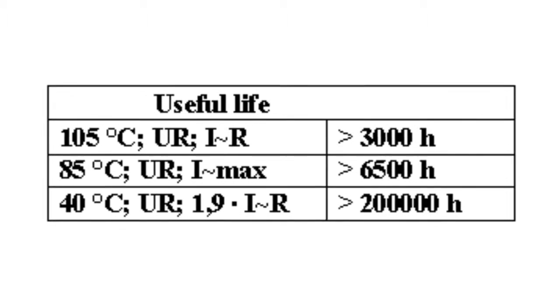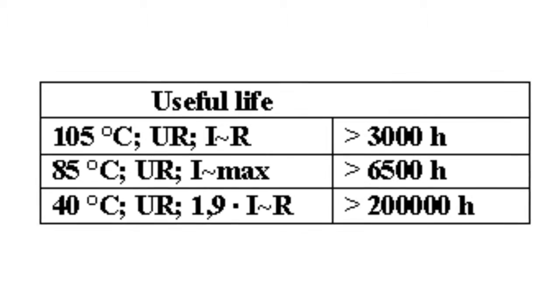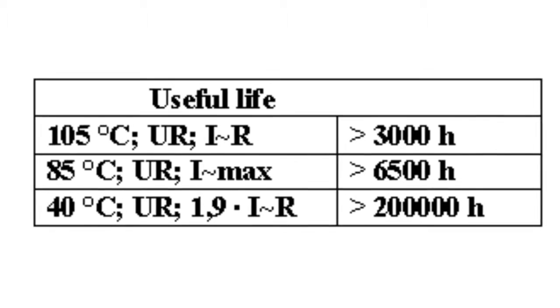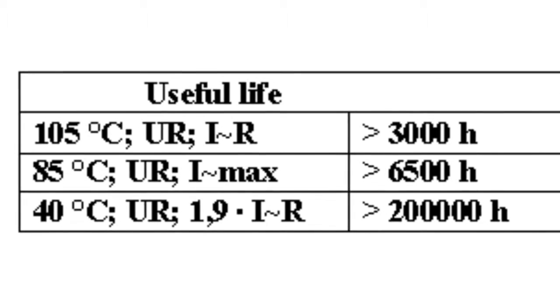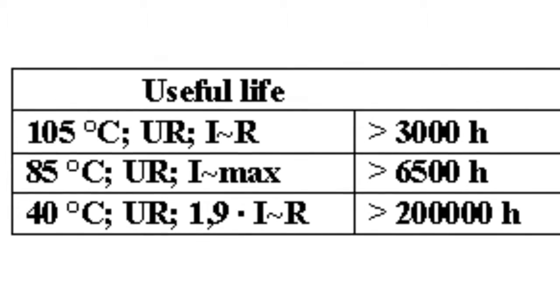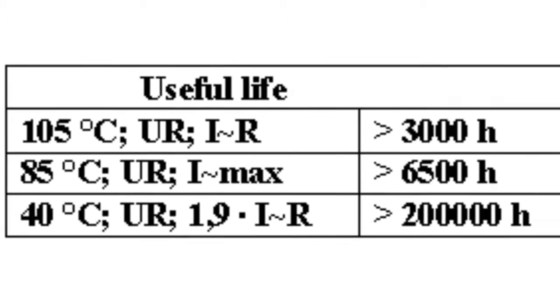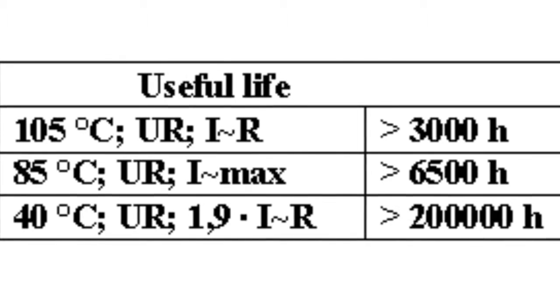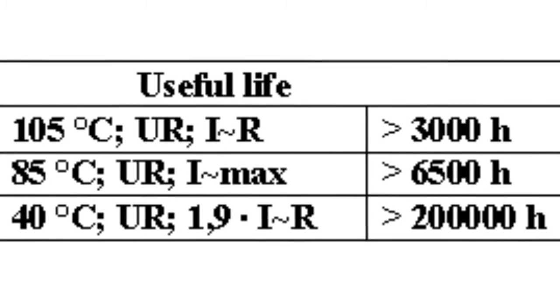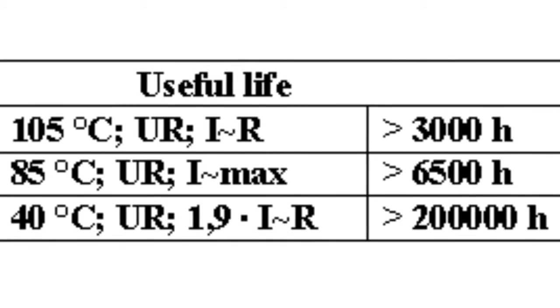Capacitors are tested for the useful life value under the following conditions: the capacitor is operating at the rated voltage, rated current, and a certain temperature — 105, 85, or 40 degrees Celsius.